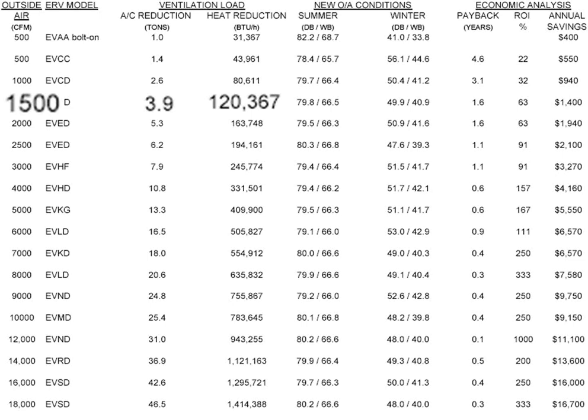On that 95 degree, 75 wet bulb, 74 wet bulb day, I'm able to get down to 80/67, which is my typical goal. And then on that minus 10 degree day, I was able to heat it up to 50 degrees incoming air, just by spinning a wheel in this case. Payback was really good, 1.6 years, 63% return on investment, life is good.